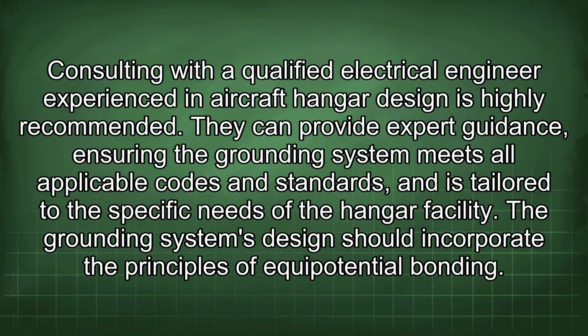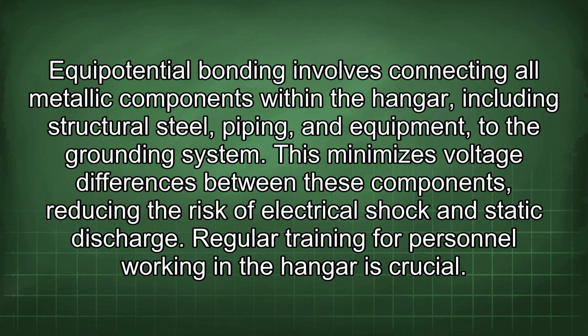The grounding system's design should incorporate the principles of equipotential bonding. Equipotential bonding involves connecting all metallic components within the hangar, including structural steel, piping, and equipment, to the grounding system. This minimizes voltage differences between these components, reducing the risk of electrical shock and static discharge.